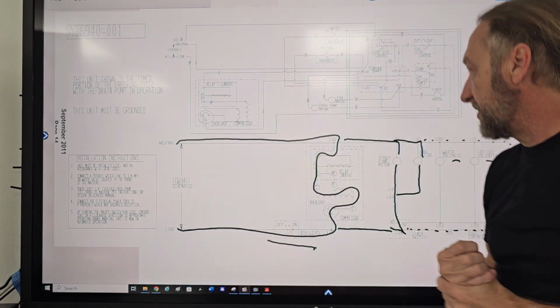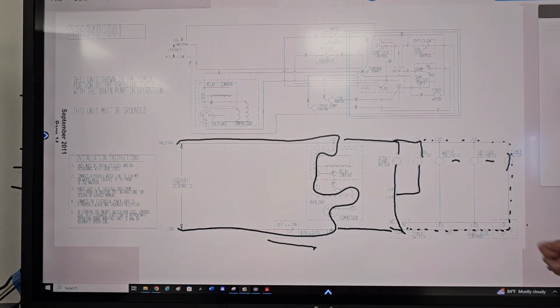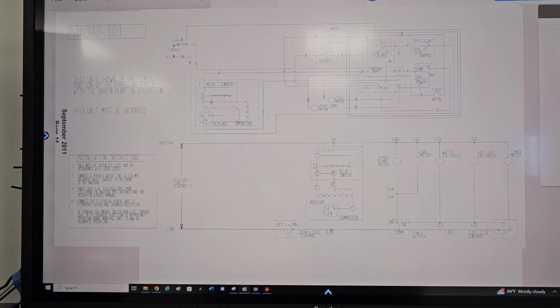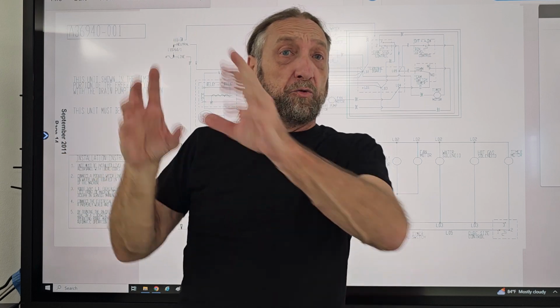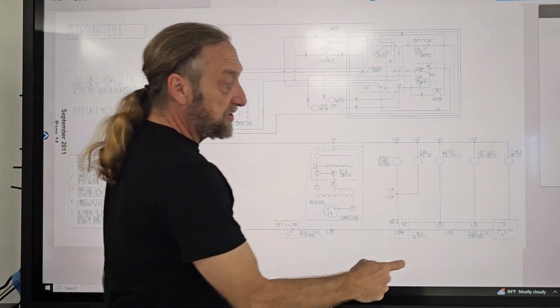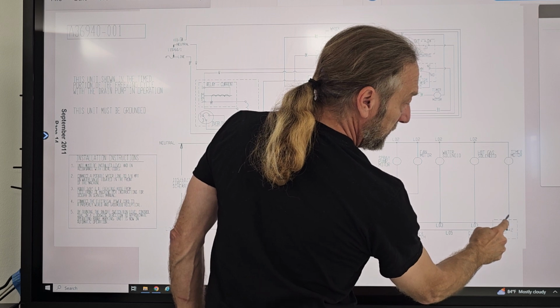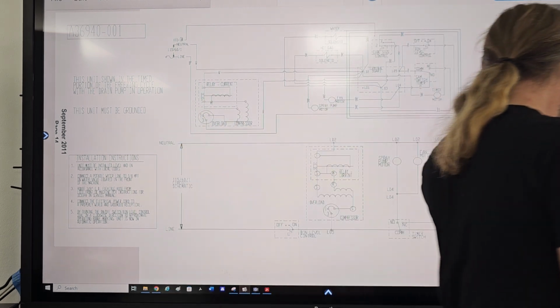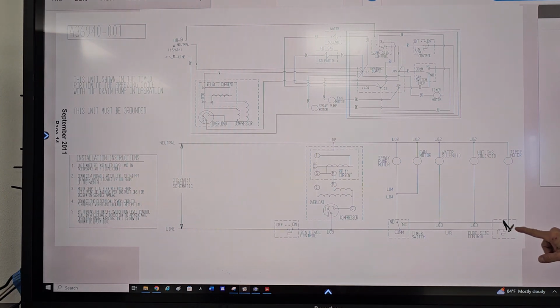So once the ice production is done, we have here this cube size control. And I'm going to say, okay, the evaporator's filled with ice right now. We're ready to drop ice. We got the size cubes we want. This thermostat is going to switch from 2 to 3. If I switch from 2 to 3, then there's no power here. That doesn't affect these components, does it? No. What affects these components is when it's running, power goes to the timer motor. The timer motor will then switch this switch over to here.